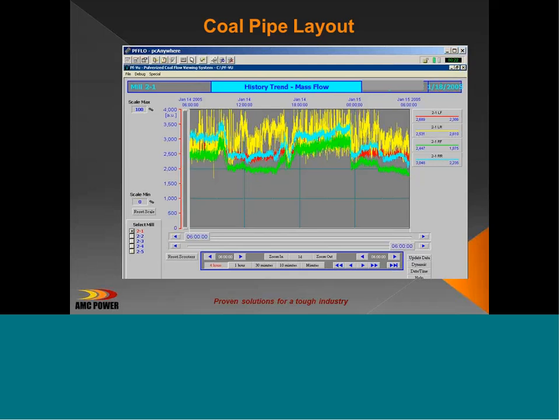The data is always somewhat erratic. Coal flow in a coal pipe is not like water coming out of a garden hose at 45 pounds pressure. Coal particles moving in a coal pipe at, say, 10 to 12 inches of water are going to be bouncing around. It's a very erratic process. While we could filter some of that out, we choose not to. We want to look at those raw signals.